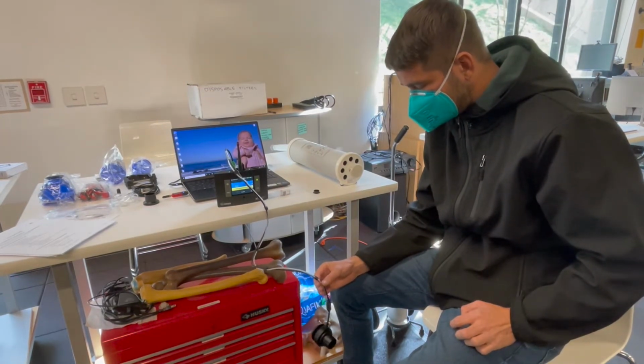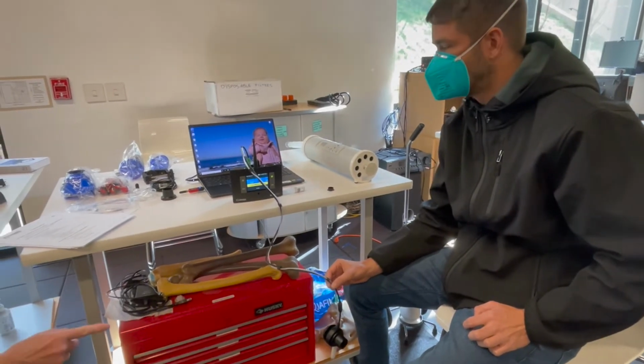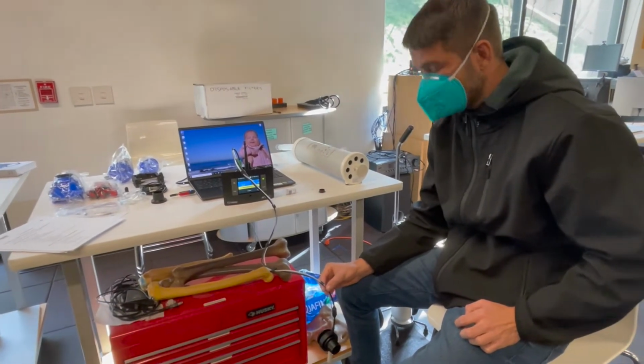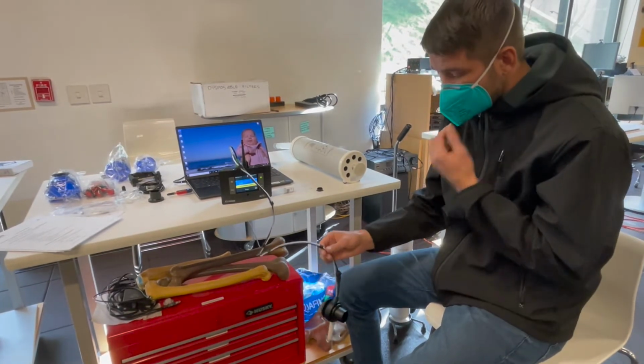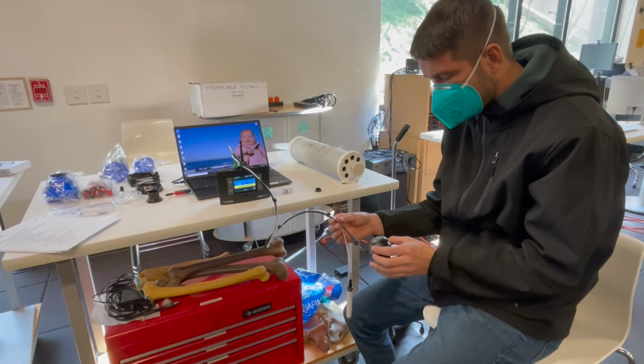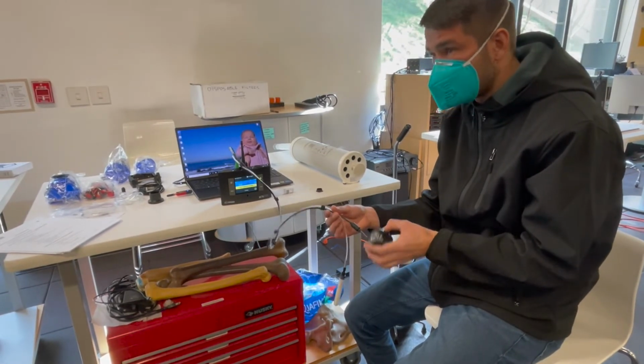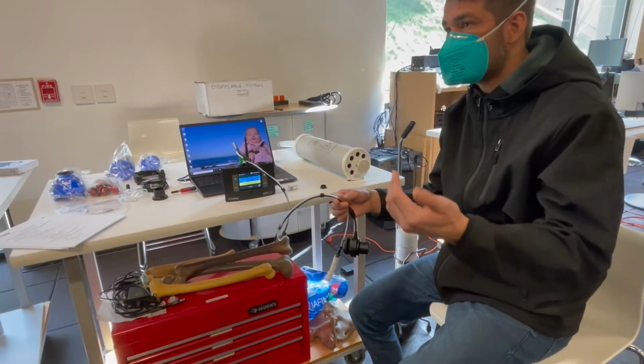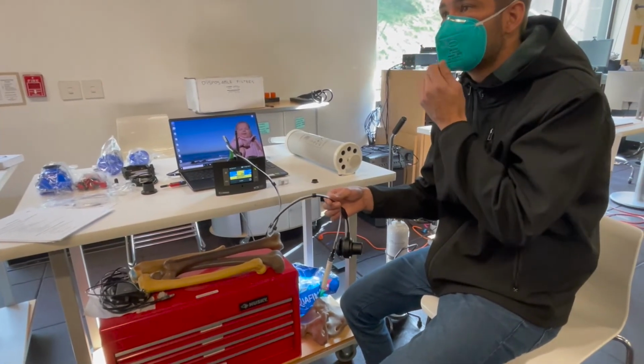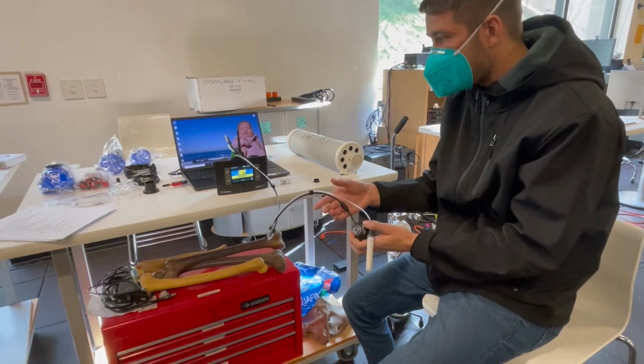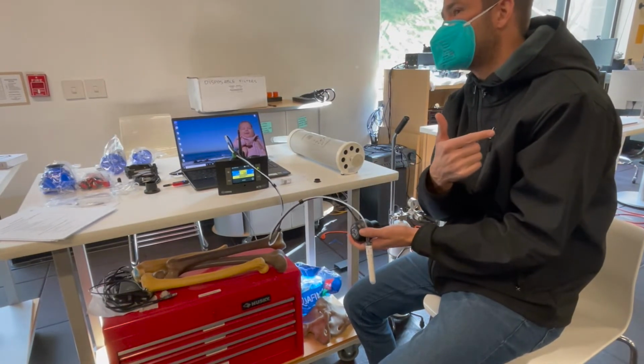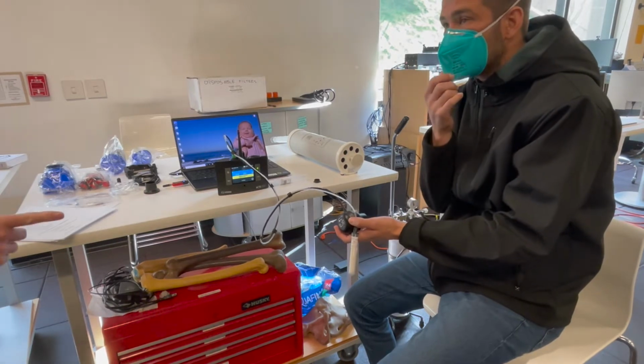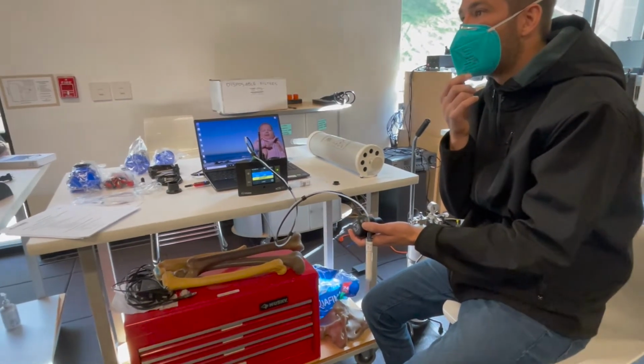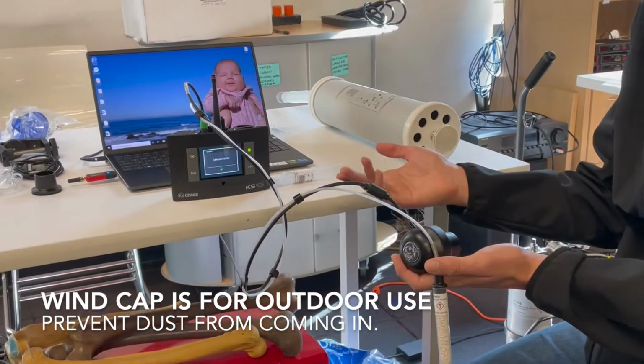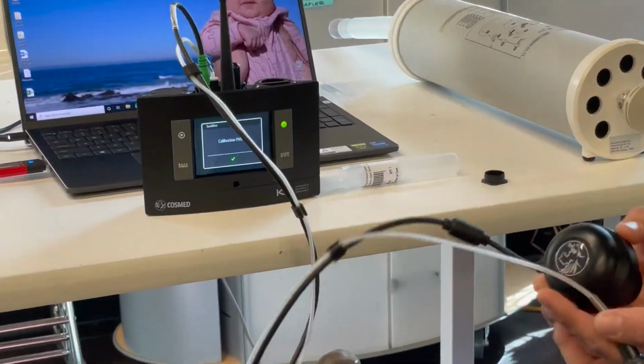While that's running, we're not so familiar with using that cap, which you mentioned before. Yeah, the wind cap, it only comes with one wind cap, and the reason for it is to prevent error in your ventilatory measurement if you're outside and the wind's blowing. We do make other caps, and the cap you got with the CPET is probably just an open cap. We have one of those in the cupboards, but we've never used it. Indoors, it's really just for the K5 for outdoor testing. But it's not going to interfere with anything.